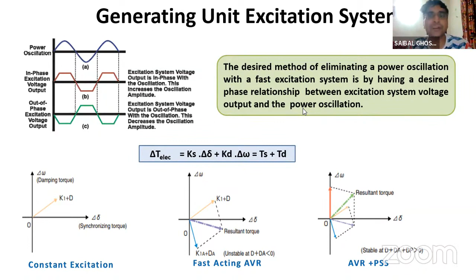Because a fast AVR improves the transient stability. In the first stage, when a fault happens, the voltage of the system is depressed, and using a fast AVR with a high initial response, the generator tries to improve the system voltage. So that is helpful. It is not negative, but sometimes it can lead you to the negative damping region. At that time, using another supplementary control, you can nullify that effect, and overall the system performance will be very good.